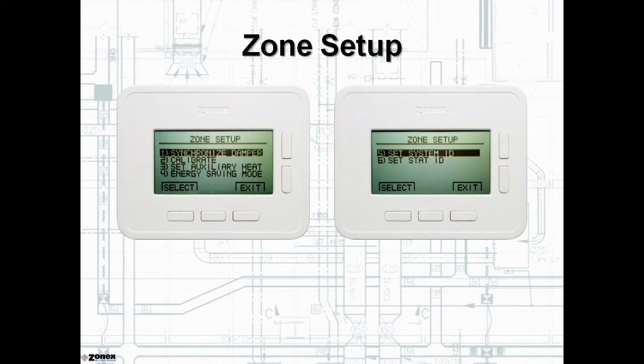Each zone thermostat can access the monitor functions for viewing only and cannot make changes. The zone setup menu, shown on the screen, is accessible from each thermostat to sync its respective zone damper, or to calibrate that thermostat if required. You can also initiate aux heat or reheat options at that zone, or initiate an energy saving selection, or set the stat and system ID.